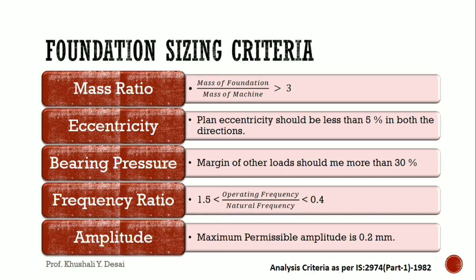Next, frequency ratio. The ratio of operating frequency to natural frequency is termed as frequency ratio. It should be either less than 0.4 or greater than 1.5 to avoid resonance condition. Amplitude: the maximum permissible amplitude, as per the code, is 0.2 mm or 200 micron.